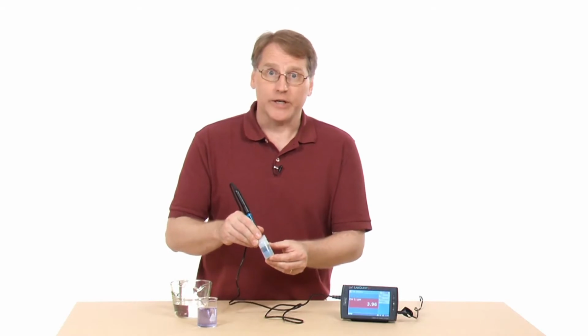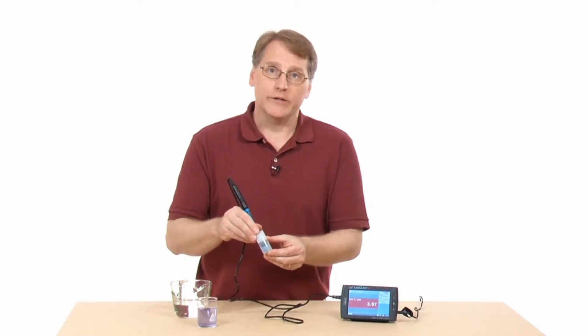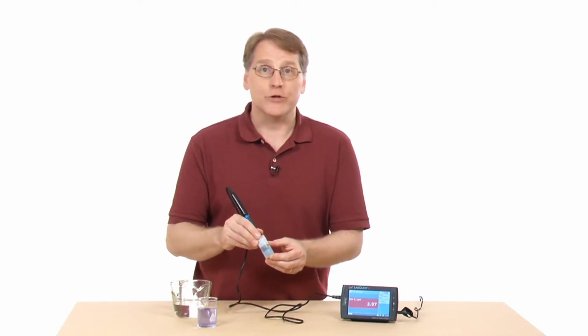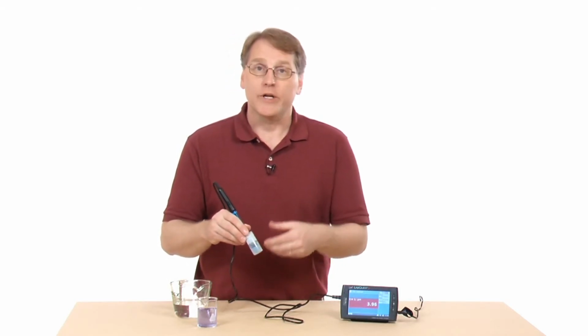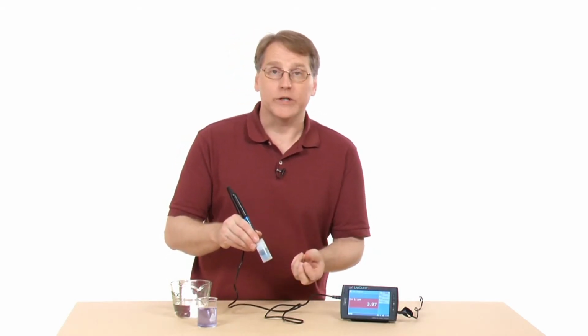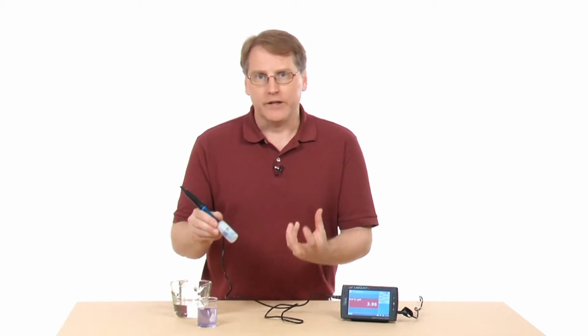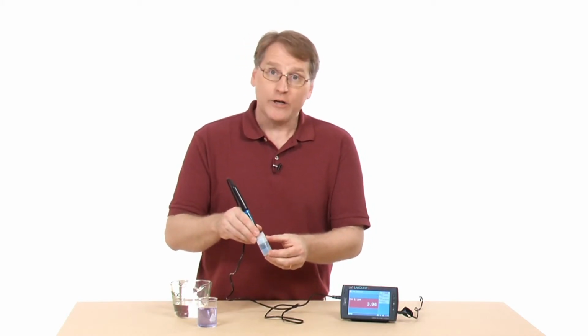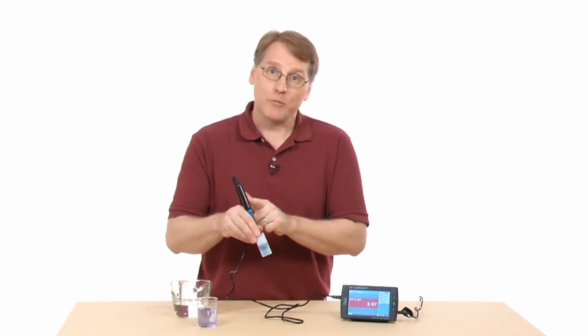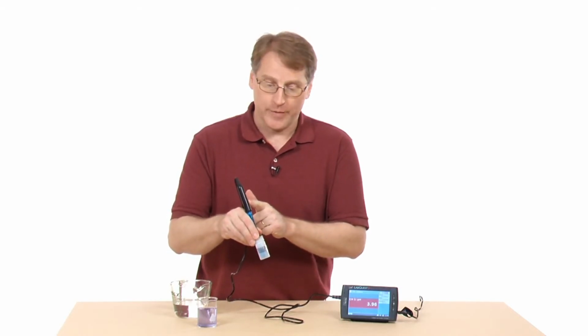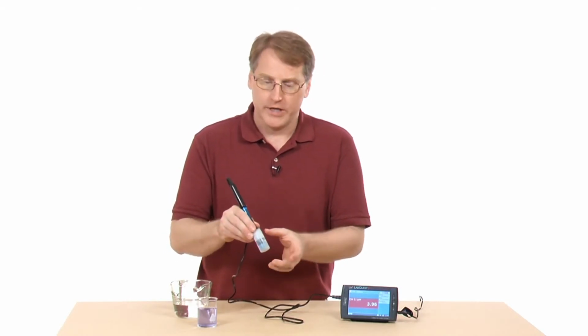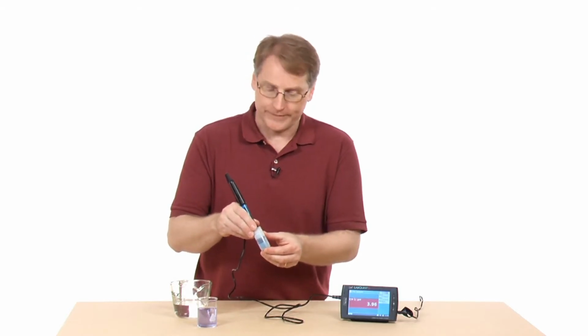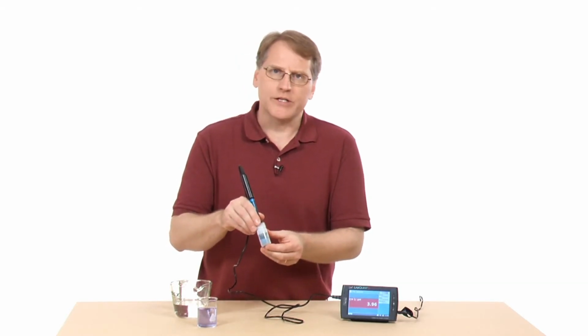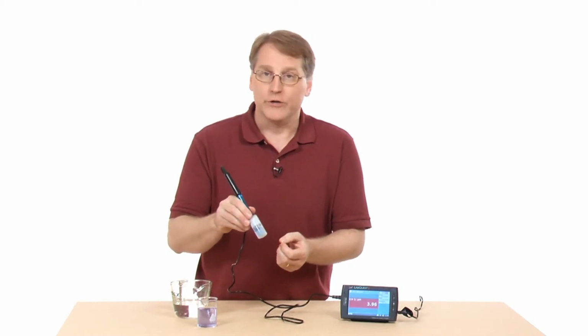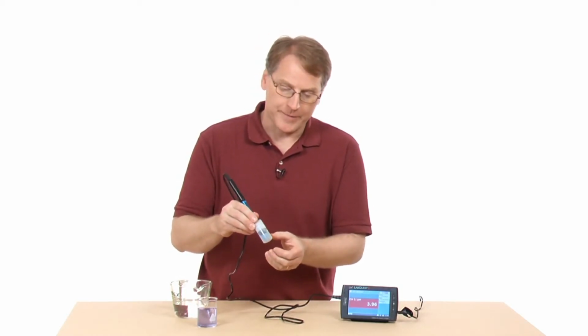You can calibrate it if you want to, and to do this, you put it into known conditions. So you might put it into a pH-4 buffer solution and tell it that's what it is, and then move it into, say, a 10, tell it that's what it is. And then you can actually store that to the sensor. This is a smart sensor that has built-in storage capacity, and so you can tell it that's what it was, and then actually save that calibration. Sometimes as these age, the values can shift a little bit, and so maybe once a year you do calibrate and be able to do that.